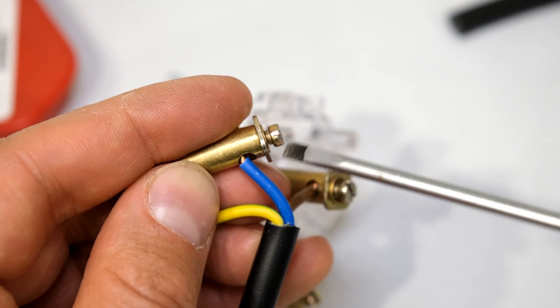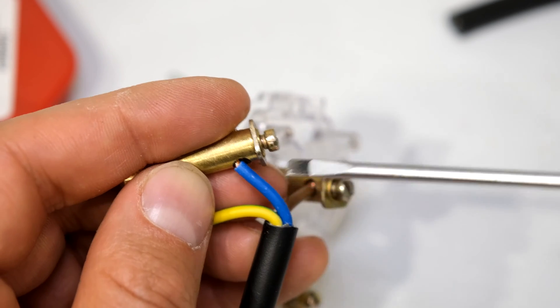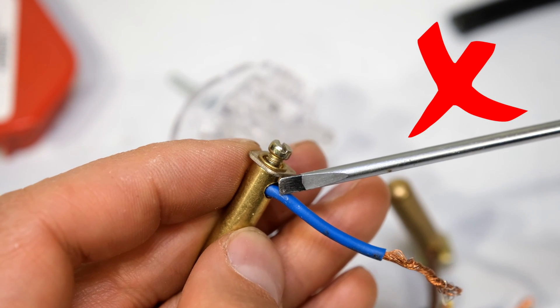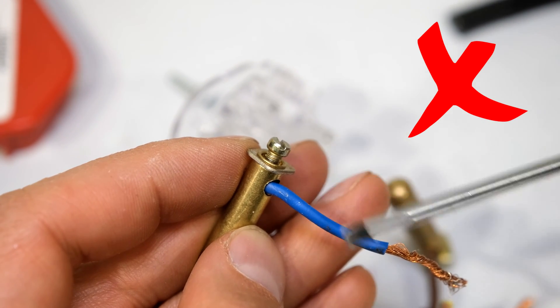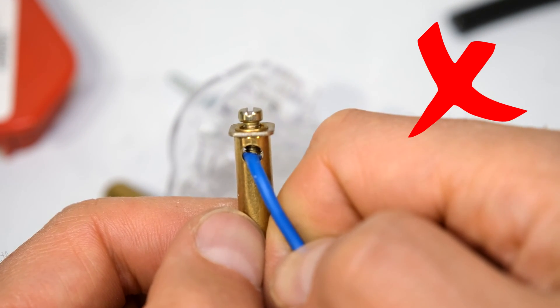Please note that the screw must fasten onto the copper. The screw must not fasten onto the jacket. If the screw is only fastened onto the jacket, it will cause arcing and heating of this wire. For example, if you look inside there, you can see that the screw is fastened onto the jacket. That is incorrect.